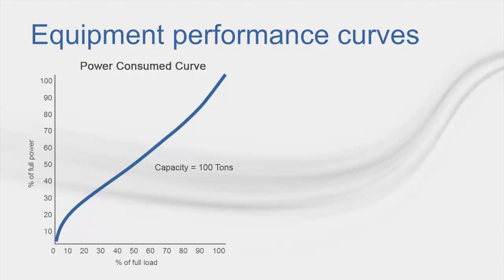As you can see in the example for the power consume curve, this would set the peak for the curve at 100 kW when the equipment was fully loaded at 100 tons, given the equipment full load energy rate of 1 kW per ton. For this example, these curves describe the energy consumption for the compressor portion of the equipment alone.